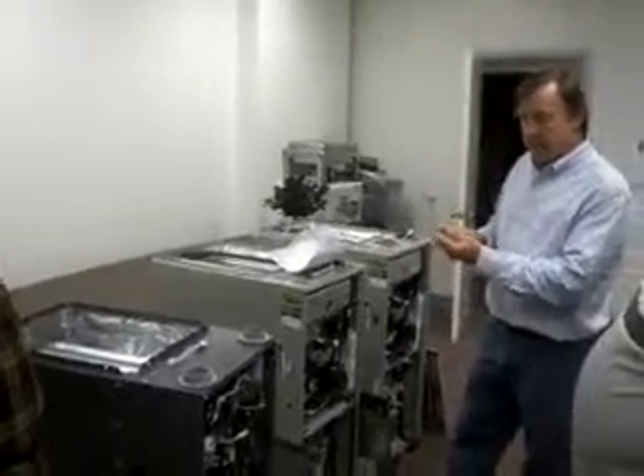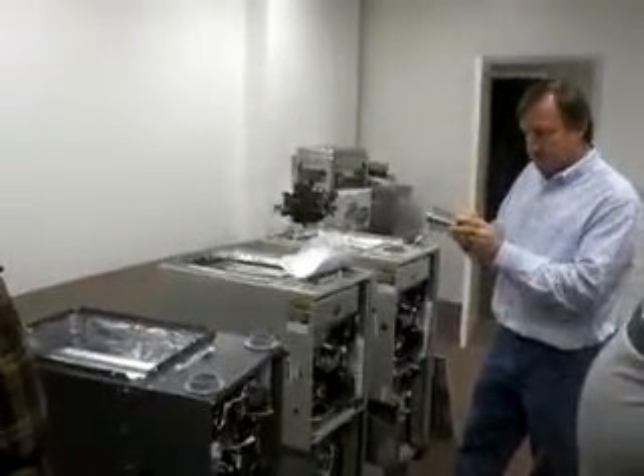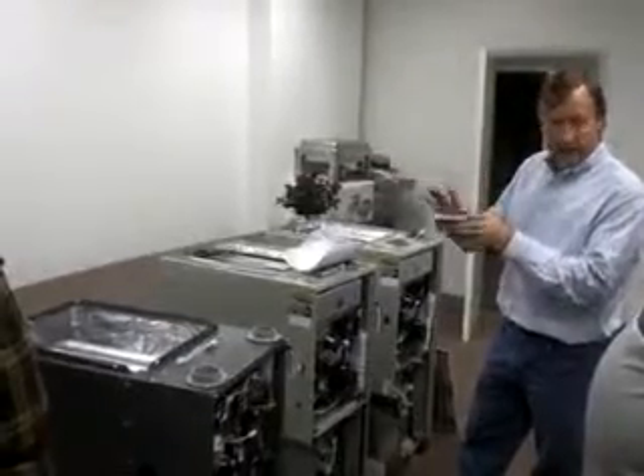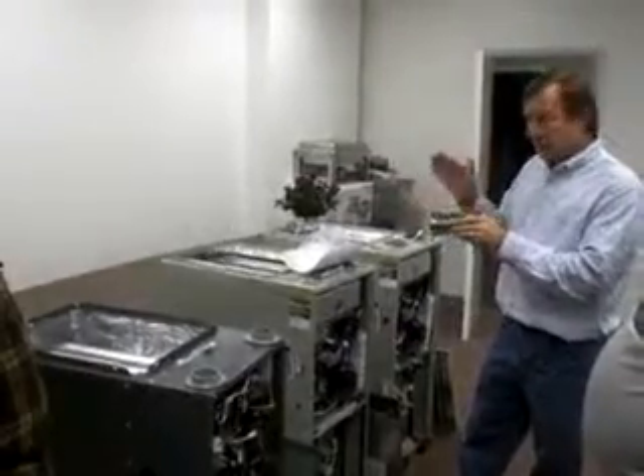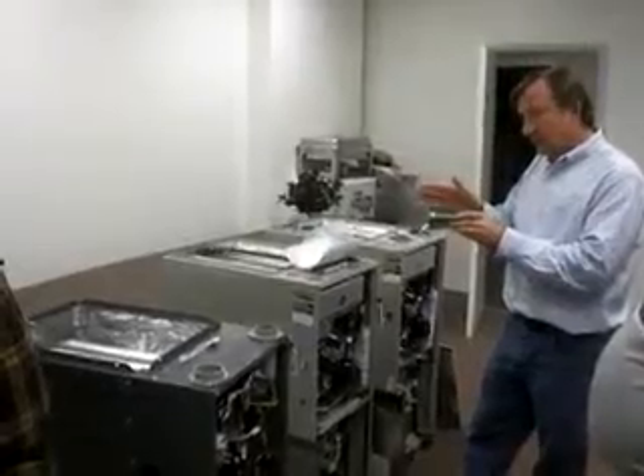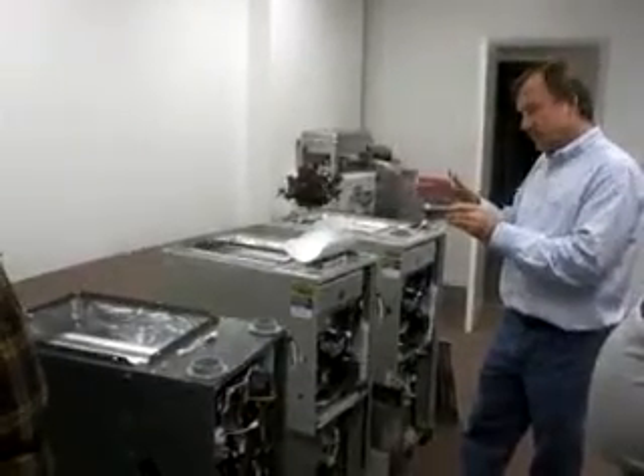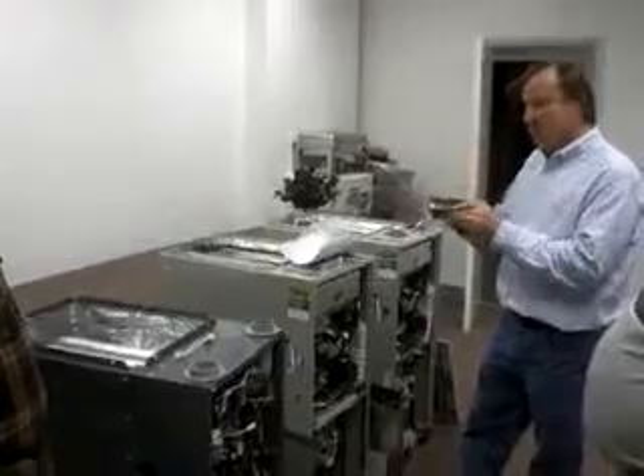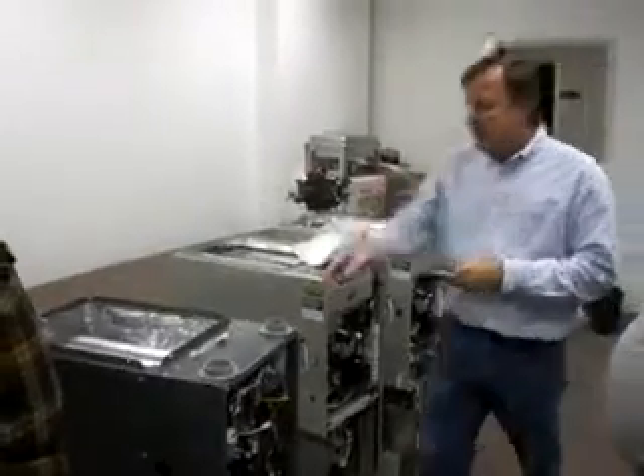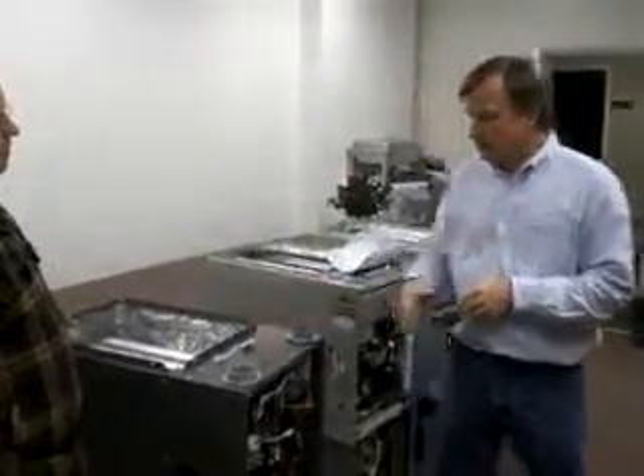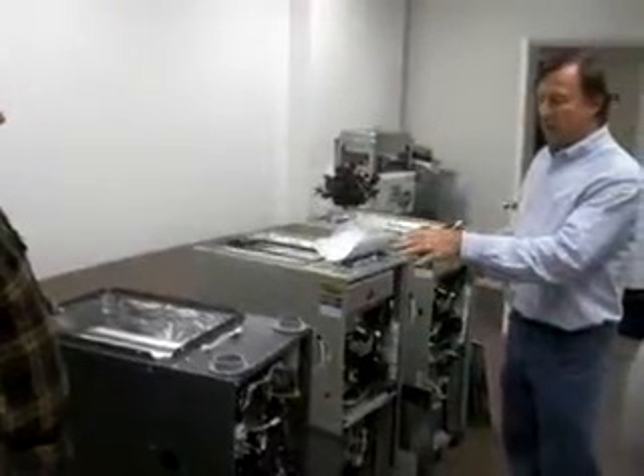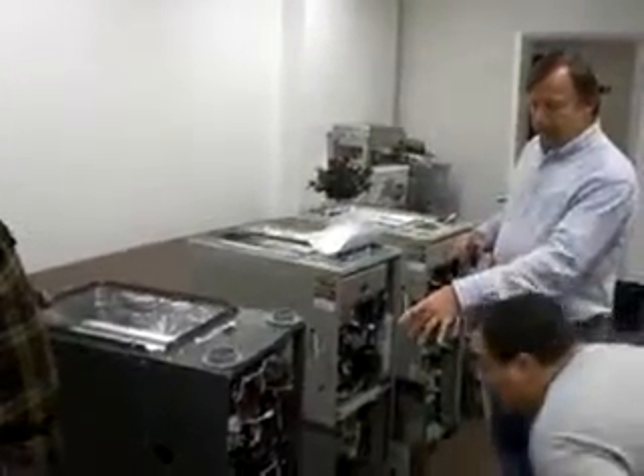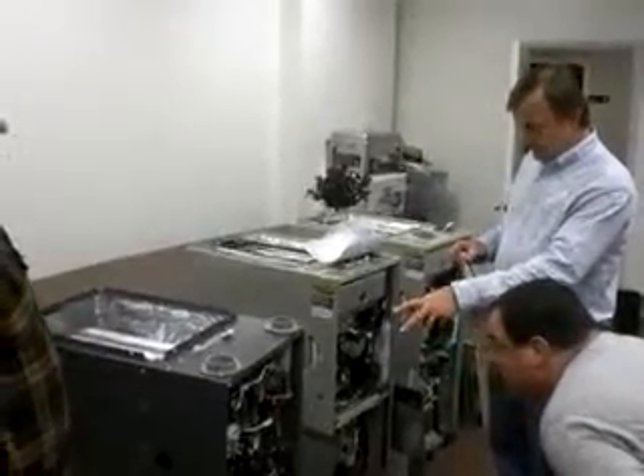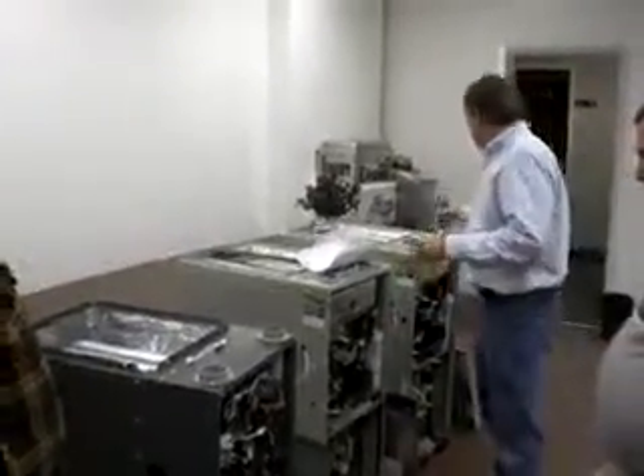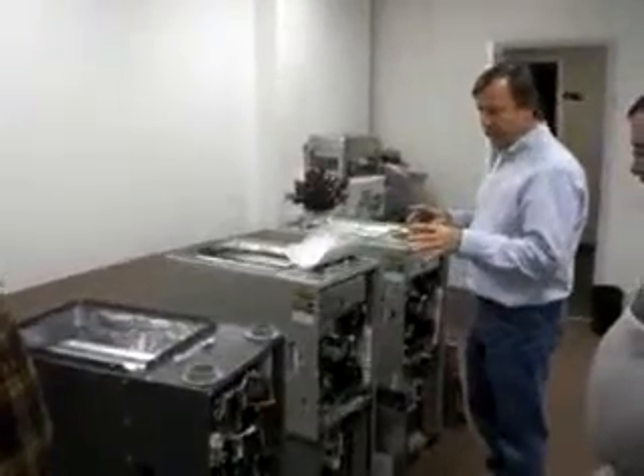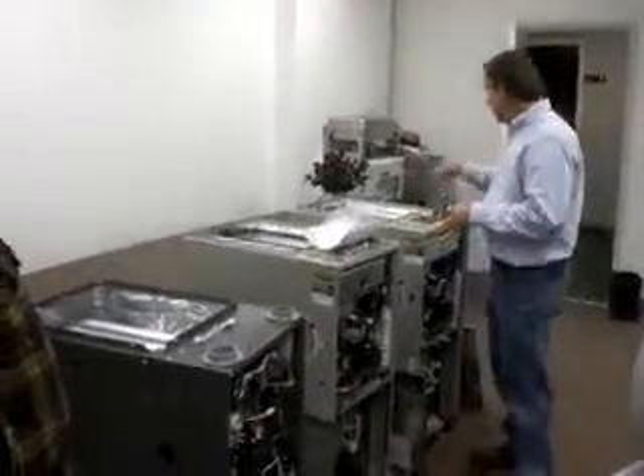The noise that's generated by one burner, okay, is the loudest that can be heard when the system is operating. You do not accumulate decibels as you introduce burners. So the smaller the burner, the lower the noise. Competitor is a larger burner, more noise. Larger burner, more combustion noise. Higher velocity fan, more fan noise. Another big difference between Trane and competition.